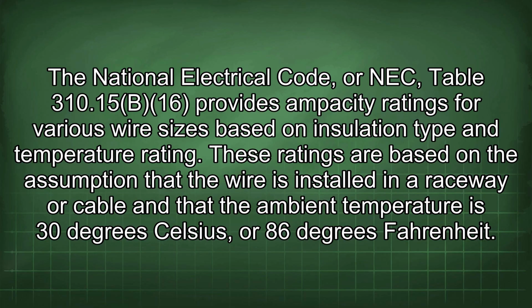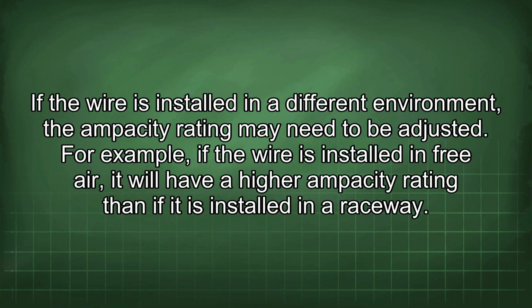The National Electrical Code, or NEC, Table 310.15(B)(16) provides ampacity ratings for various wire sizes based on insulation type and temperature rating. These ratings are based on the assumption that the wire is installed in a raceway or cable and that the ambient temperature is 30 degrees Celsius or 86 degrees Fahrenheit. If the wire is installed in a different environment, the ampacity rating may need to be adjusted. For example, if the wire is installed in free air, it will have a higher ampacity rating than if it is installed in a raceway.